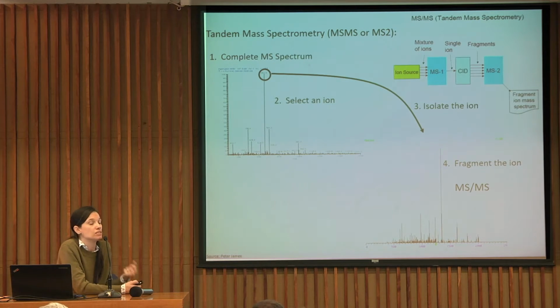In the case of MALDI, the selection of the ions is manual. You will choose an ion that has high intensity and that is separated from its neighboring ions. In the case of an instrument like the Q-Exactive, you set up a method where you tell the instrument to select the 15 or 10 most intense MS peaks in each MS run for fragmentation. So at the end of a 2-hour run, you may have up to 60,000 MS/MS spectra that will be used for protein identification.